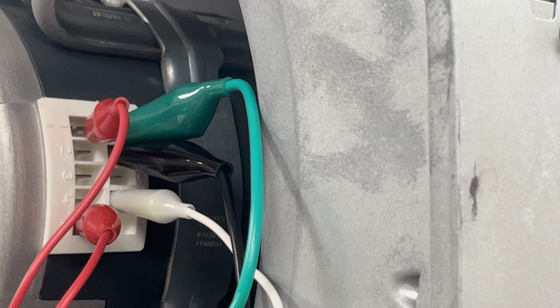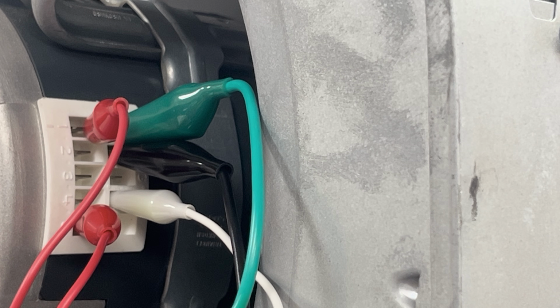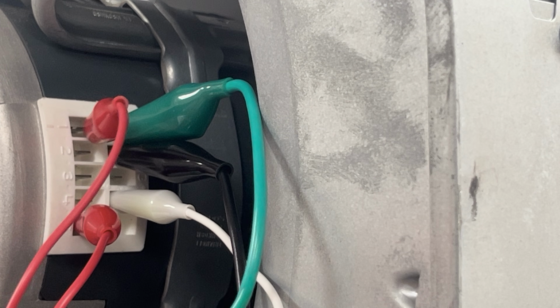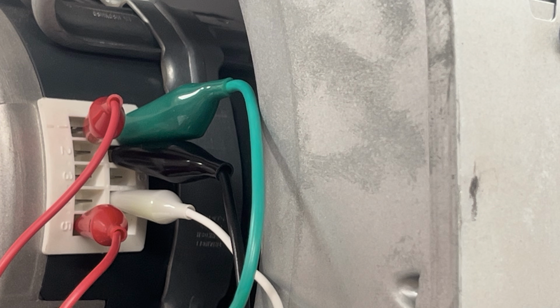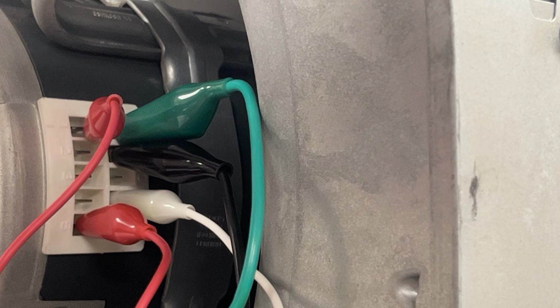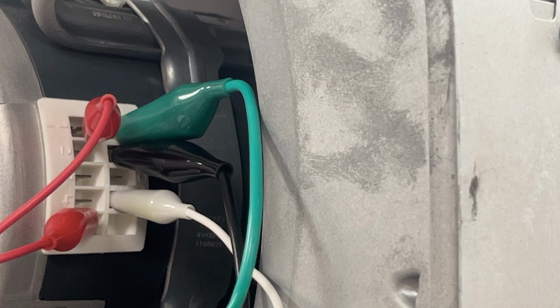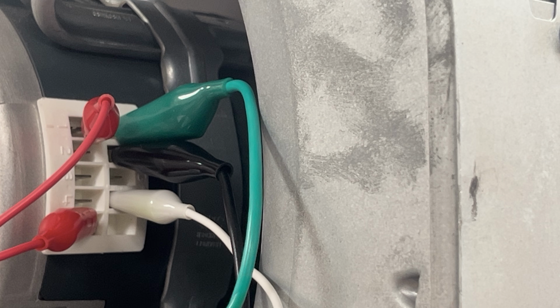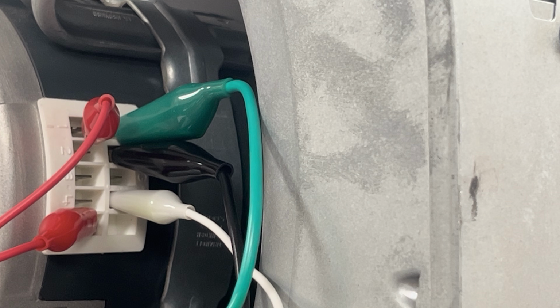Now that we have power, you'll hear the motor kick on. So now the motor is running. And we're running on speed tap 1, which is low speed. And the moment I put power on speed 5, you'll hear it kick up. And so there's still power on 1. Now I have power on 5. So the motor just revved up to its high speed.